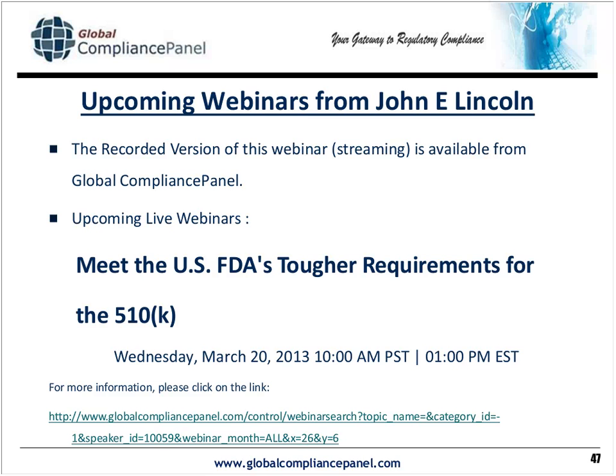You bet they can. But the point is, one thing I like to stress in some of my webinars is, if you anticipate an area of disagreement, make sure you've thought it through and you cover it by means of documentation of your rationale. I usually include that in either the validation documentation or an SOP. An example being that N = 30 sample size. Include a good rationale as to why you did the thing you did. Then what the FDA does, they may disagree with you, they may vehemently disagree with you, but they can't argue with the fact that you've looked at that issue, you've considered it, and you came up with a decision.